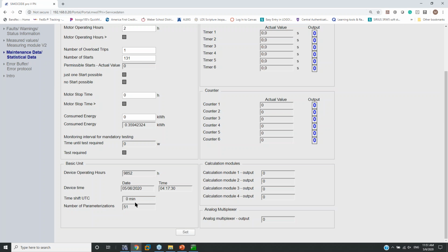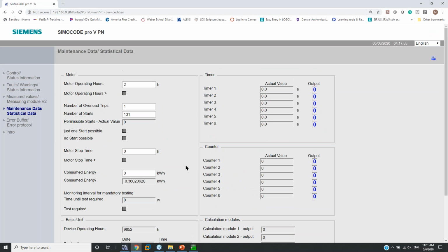Now this might get some plant manager or some process guy a little worried. Once you commission a pump and get it running, you should only see parameters change maybe 2 or 3 times, just for some specific changes. Or maybe you changed out a motor from a standard motor to a high efficiency and had to change out the full load amps. So you should only see a handful of parameter changes. Man, if you got 51, there's something seriously wrong in your process. But you can tell and get some data from that.